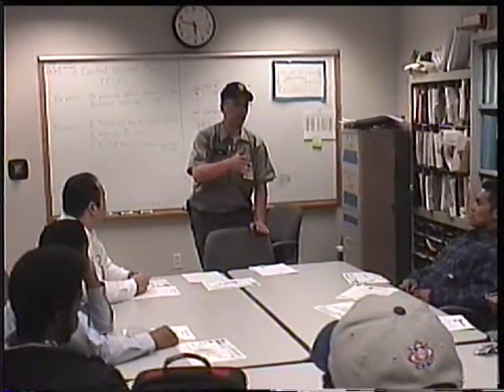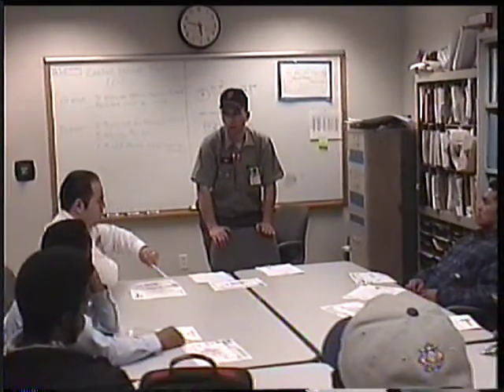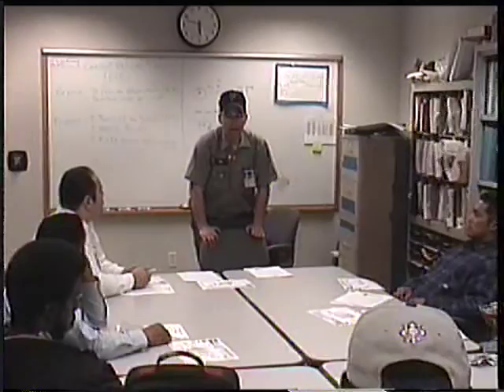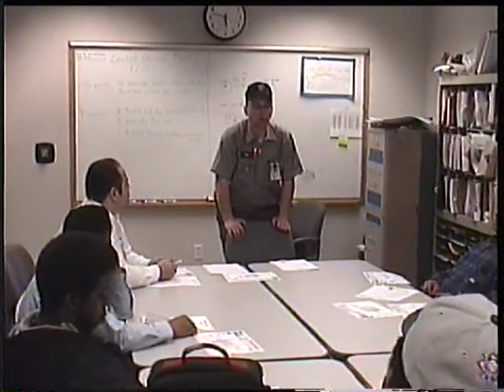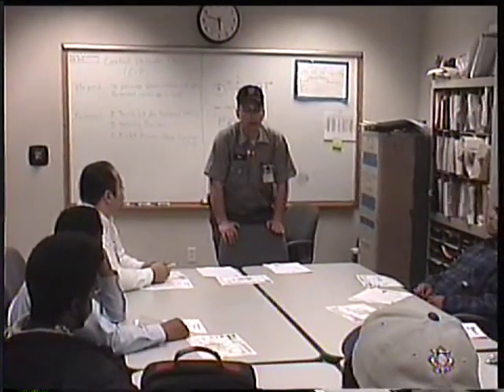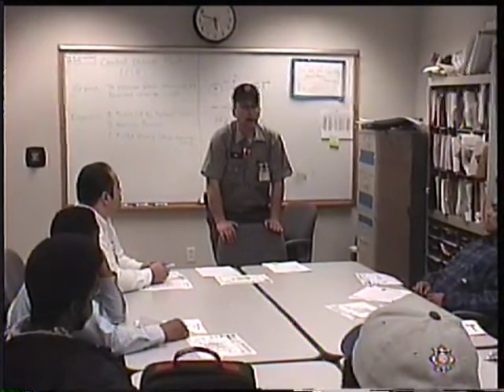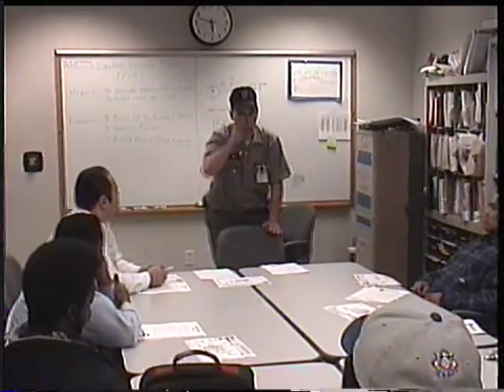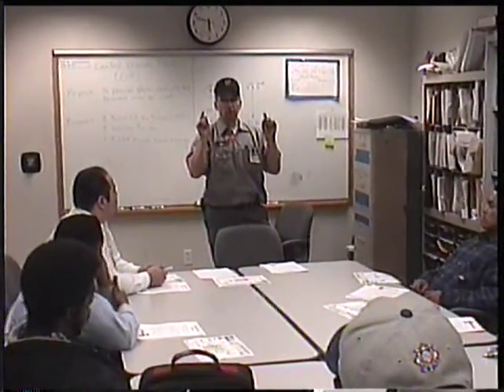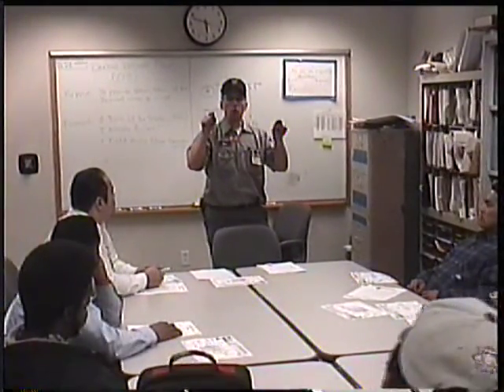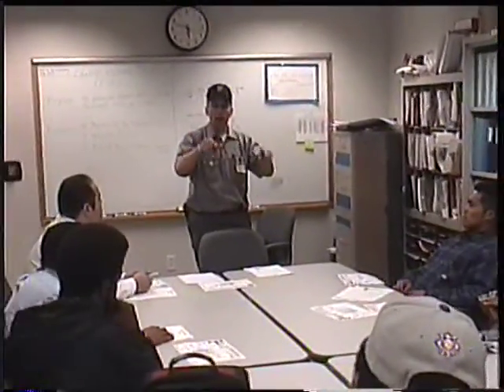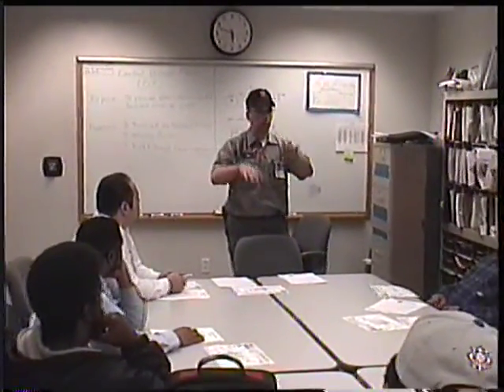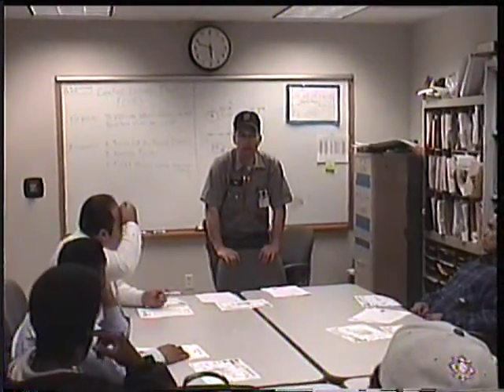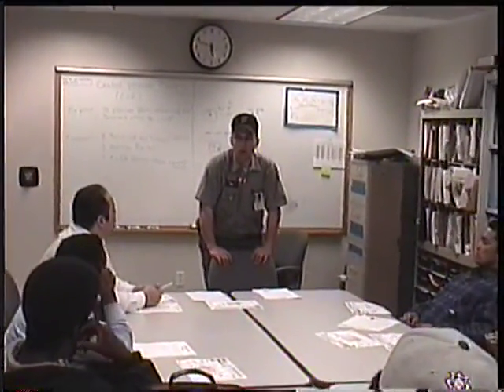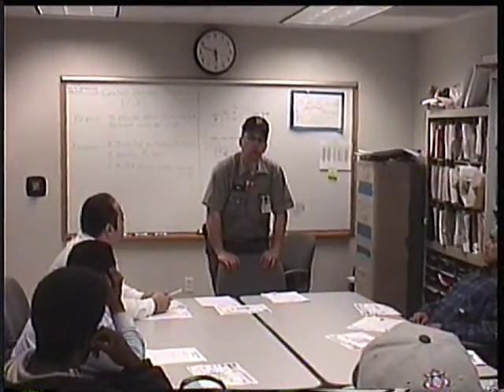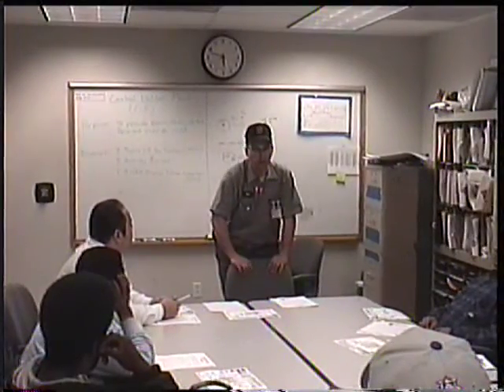They got these guys that came in. That's all they do as a livelihood, they start up plants across the country, across the world, and they didn't catch it either. So we've had a lot of problems with our auxiliary boilers as well as our HRSGs. Same problem: chemical injection. In the boilers, we actually have 2 steam drums and 2 mud drums instead of just 1 and 1. Chemicals will feed very heavy into the first 2 steam drums, but very lightly into the rear steam drums. You'll get these total chemical imbalances, and you can't really compensate because the boilers are burning up the chemicals in the A drum, and they're not getting transferred over to the B drum side. Once again, you'll see that when we go downstairs.